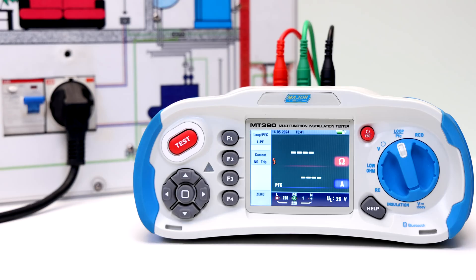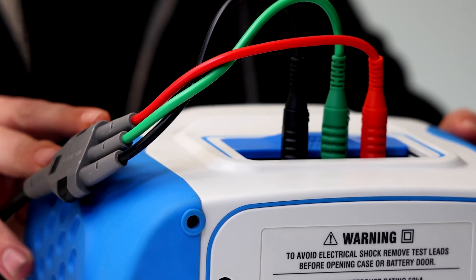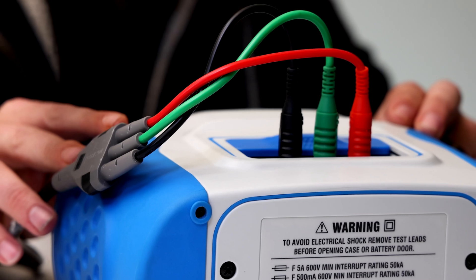Press and hold the F4 button for more than two seconds until the zero annunciator appears. The tester measures the lead resistance, stores the reading in memory, and subtracts it from the readings.